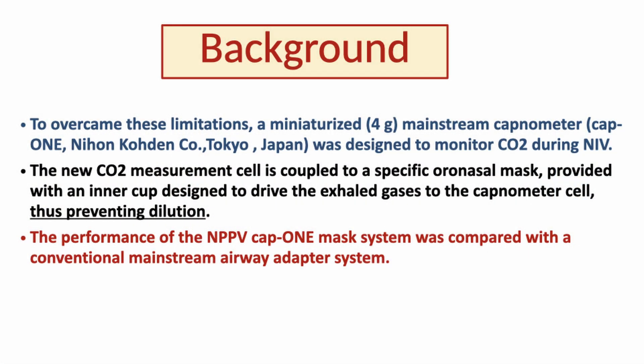To overcome this limitation, a miniaturized mainstream capnometer — very light, just four grams — has been designed by Nihon Kohden, called cap-ONE, and is expressly designed to monitor CO2 during non-invasive ventilation. This CO2 measurement cell is coupled with a specific oronasal mask that we will describe in more detail in the next slides, which is provided with an inner cup expressly designed to drive the CO2-rich exhaled gases to the capnometer cell, thus preventing the dilution effect.